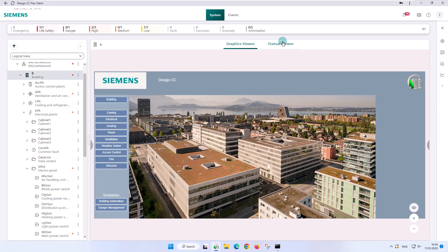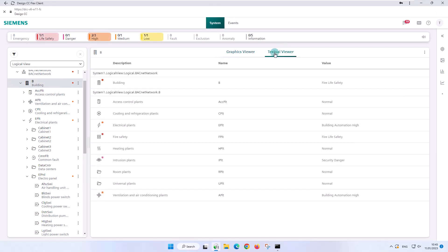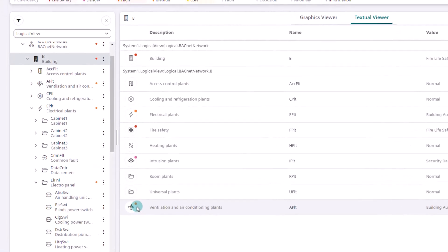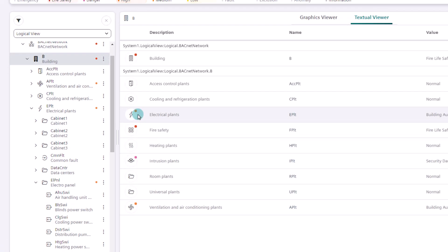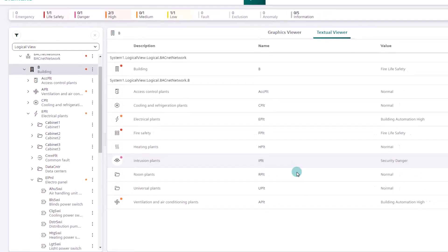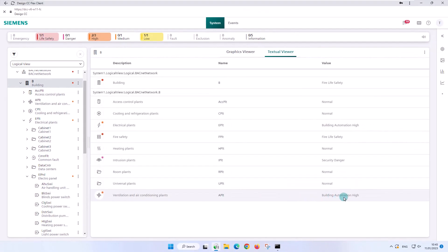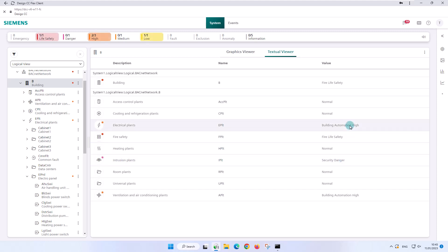In the textual viewer, we clearly represent all child objects with value display. Four objects show error messages with different priorities, including the propagation by means of a dot representing the alarm category with the corresponding color. The building object takes over the one with the highest priority, fire life safety.